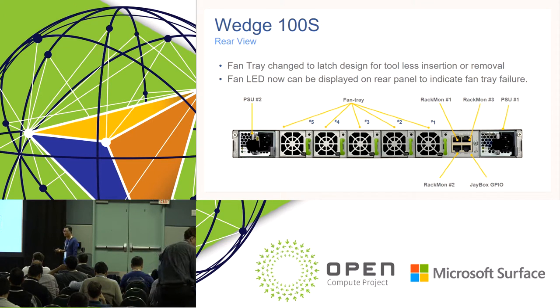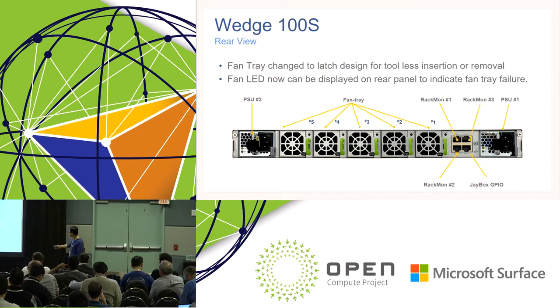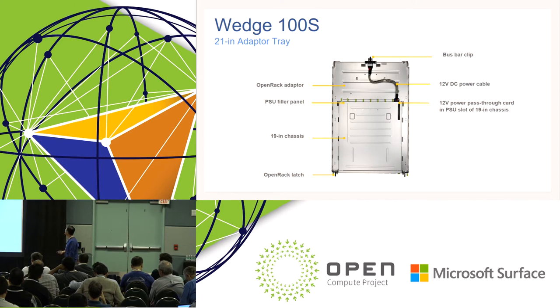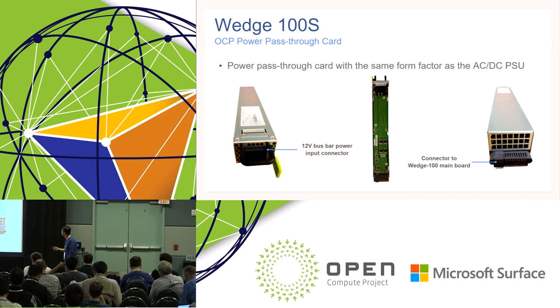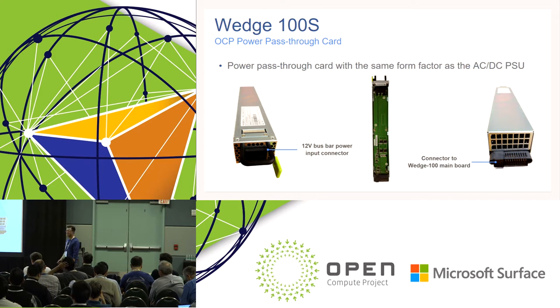There are three rack mount ports — basically serial ports with RS-485 physical signaling — connected to the rack power supply unit in OpenRack V2. There is also a JBOX GPIO port with multiple general-purpose IOs controlled by the BMC. The 21-inch adapter tray has a 12V DC power cable that connects to the rack power bus bar, and a 12V power pass-through card inside the 19-inch chassis. This power pass-through card has the exact same form factor as the AC/DC PSU. By designing this card, we can use this box in both 19-inch and 21-inch racks without modifying the box itself.